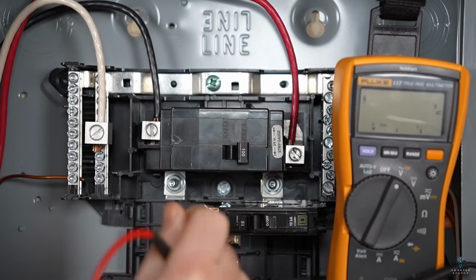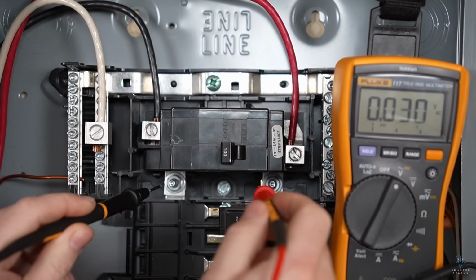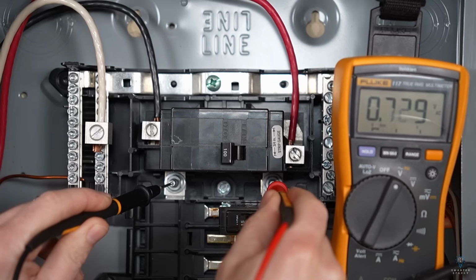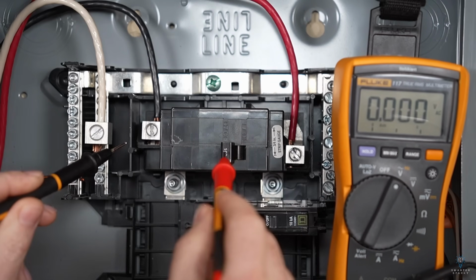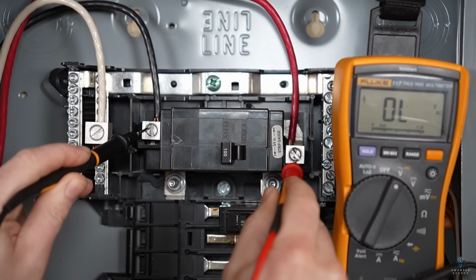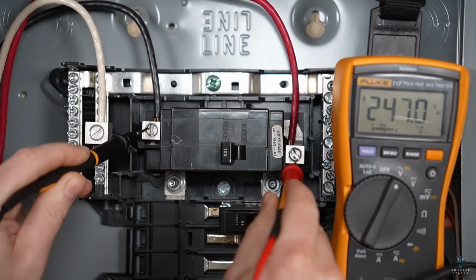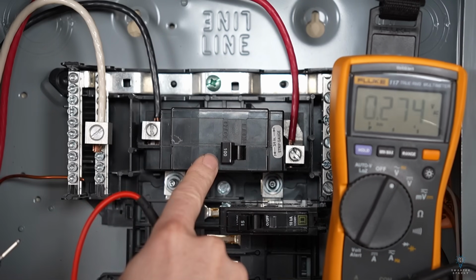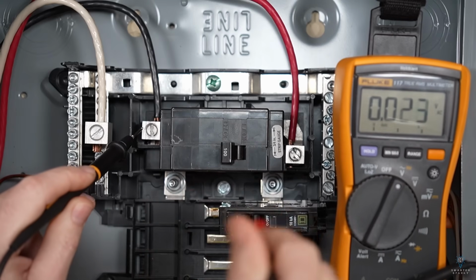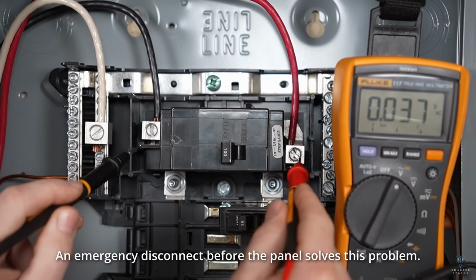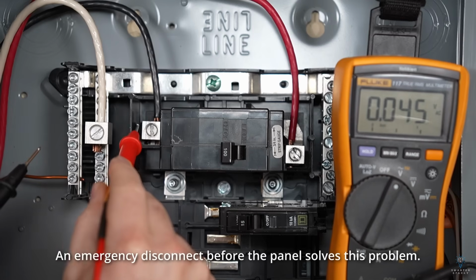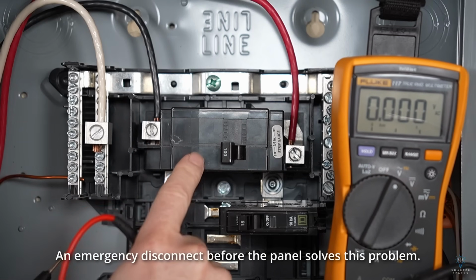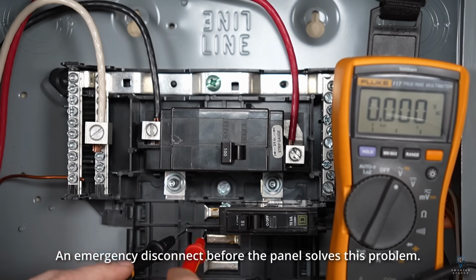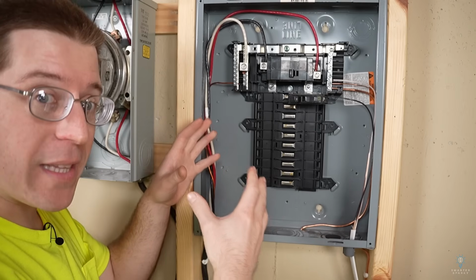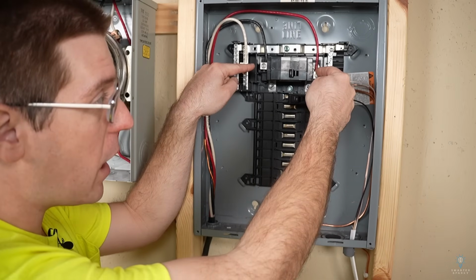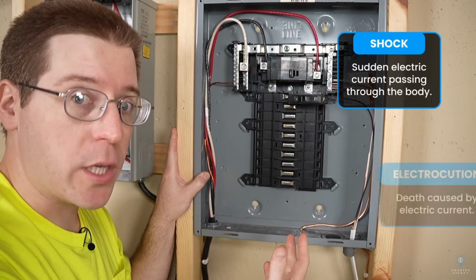If we shut the main circuit breaker off, the output from the circuit breaker is 0 volts, but we still have 240 volts coming in to the circuit breaker. So shutting this circuit breaker off does not turn off everything in this panel. These two lugs right here are still energized. Turning this breaker off only shuts off these bus bars underneath. So what that means is touching these two lugs could result in shock or electrocution.